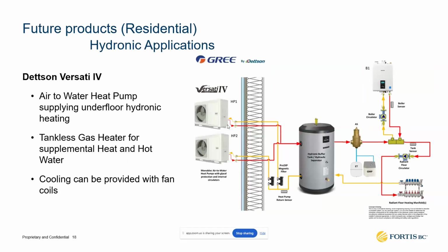Now, this is another system that I wanted to share with you today. We don't have an incentive for this type of system yet, but it is in the works. It's probably going to happen by the end of this year or sometime next year. We're working on the business case for the pilot program. This is a heat pump hybrid solution, a dual fuel solution for hydronic applications. In this system, again, our electrical component is an air source heat pump. In this case, it's an air-to-water heat pump that supplies a hydronic loop, and this is usually used in radiant floor heating applications. And again, the additional heating, if required, comes from a tankless boiler that can also provide domestic hot water to your home.